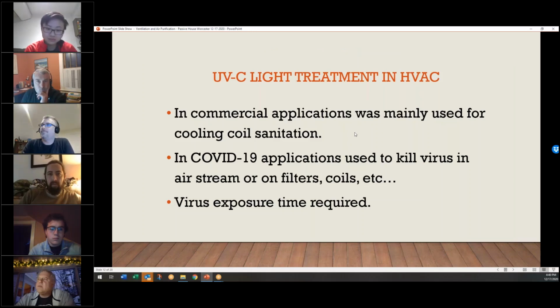Okay, so after filtration, something that's been vetted for many years is UV light, right? And UVC, meaning it's the C band of UV light, just above sunburn level, I think, is one above, and then there's UVA on the other side of it. But UVC light has been used a lot in HVAC over the years, mainly for keeping your coil clean, keeping mold and bacteria from growing on your cooling coil. So it was used in that application, not necessarily to try and sterilize air. Not that it wasn't used that way.